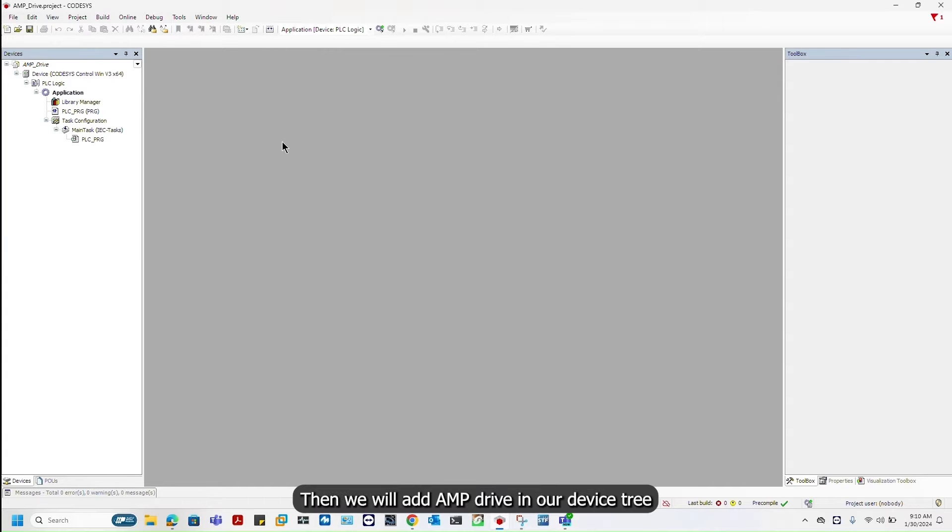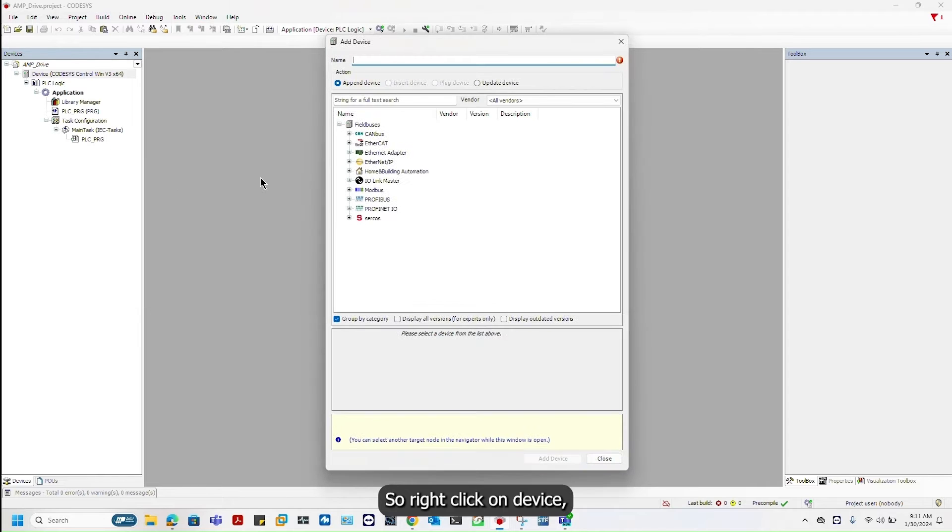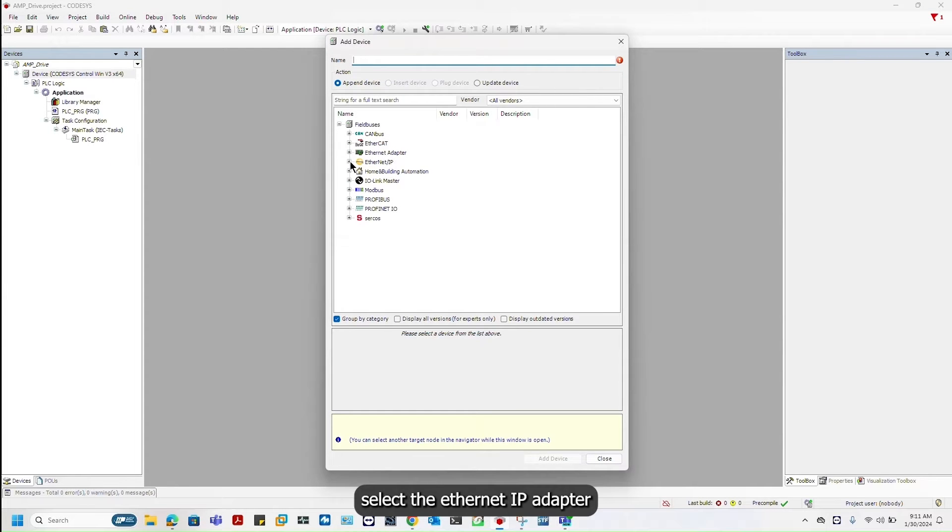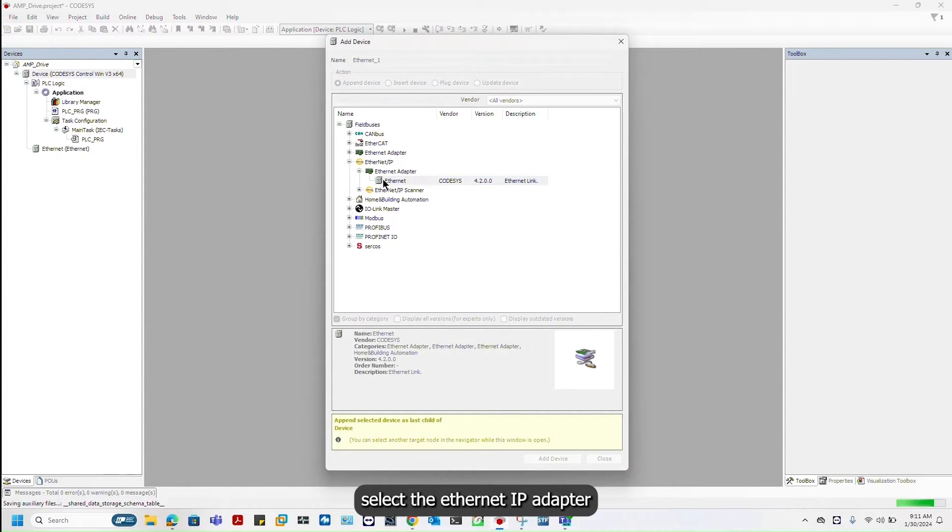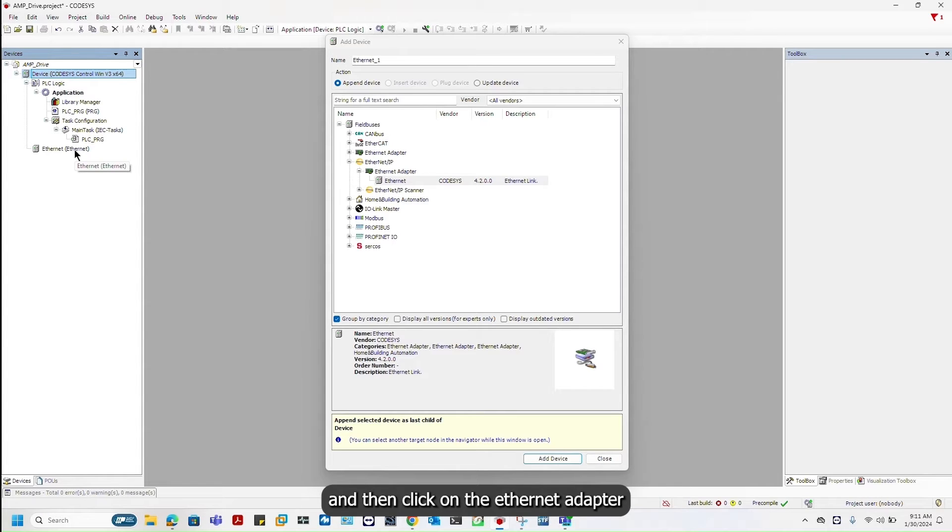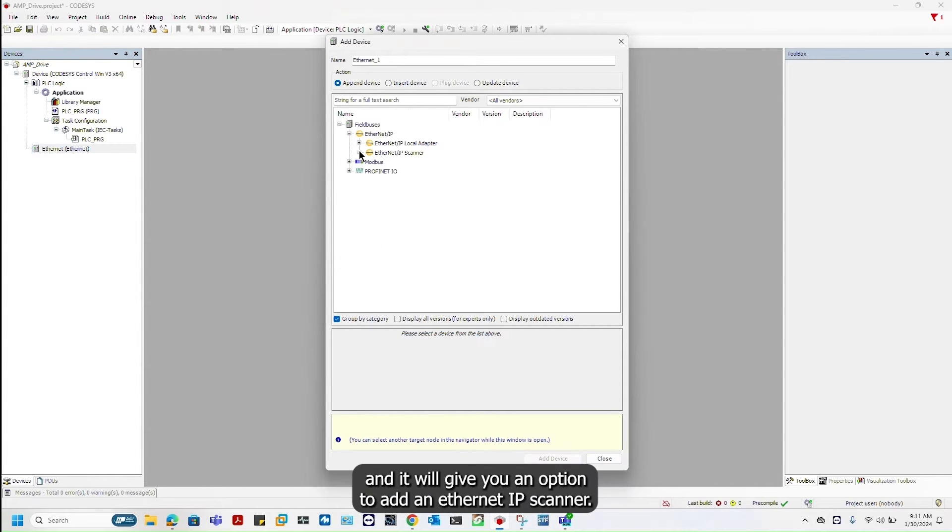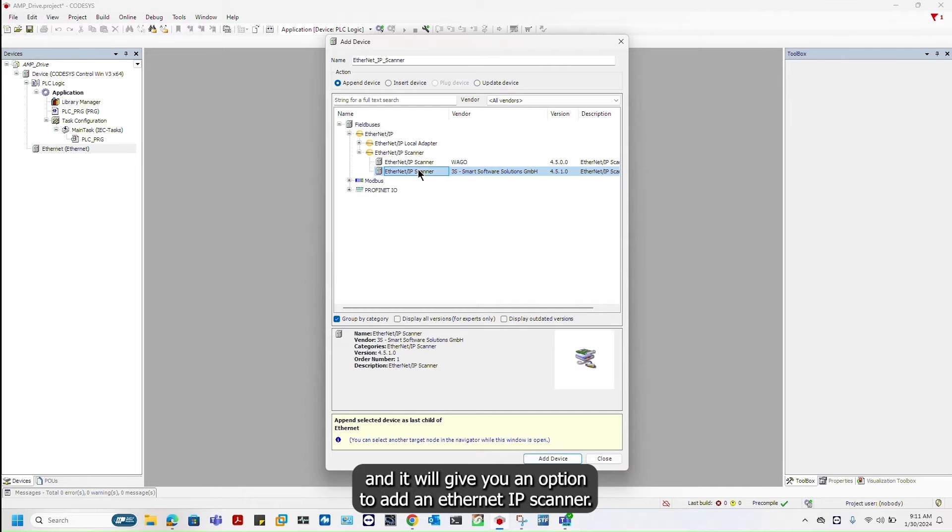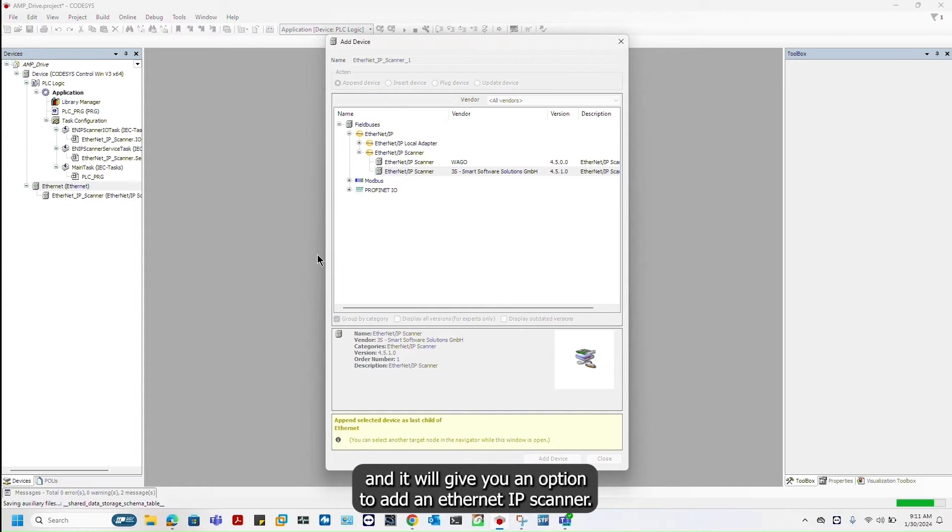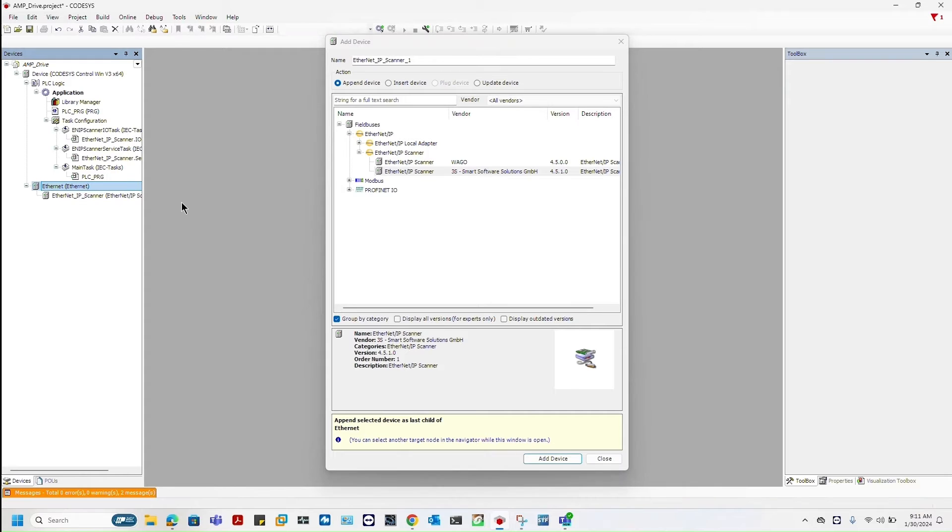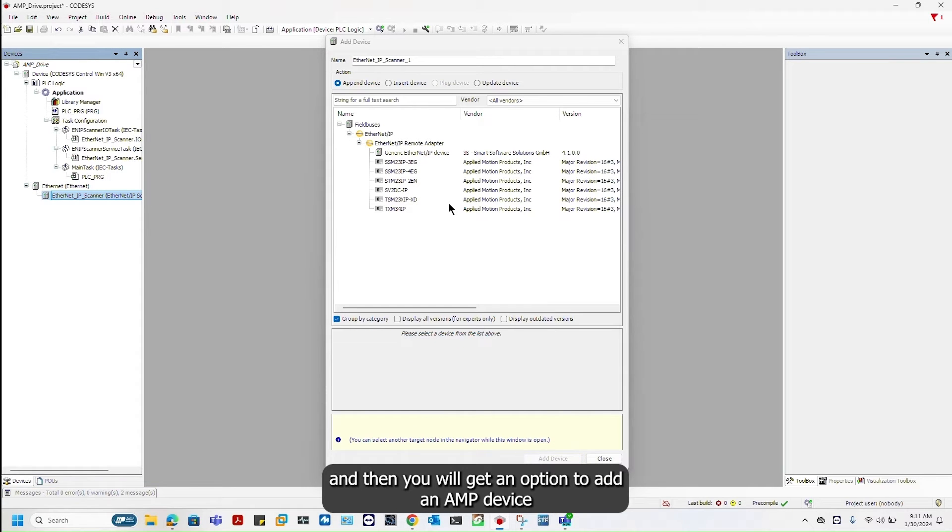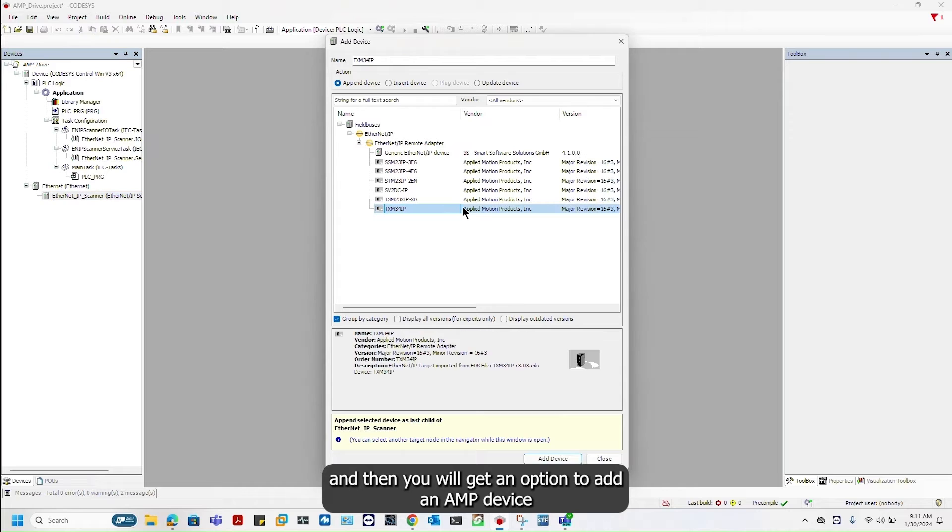Then we will add an AMP drive in our device tree. Right click on device, select the Ethernet IP adapter. Click on the Ethernet adapter and it will give you an option to add an Ethernet IP scanner. Click on the scanner and you will get an option to add an AMP device.